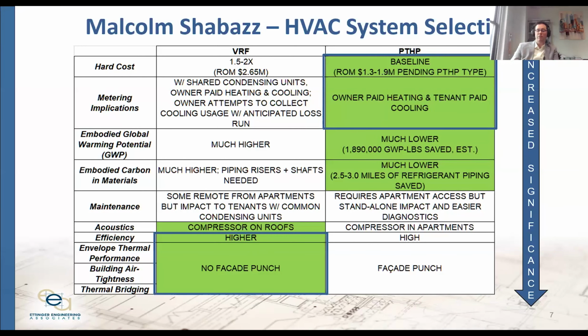there are two prime benefits that a development like this would seek to gain. First, without all of this refrigerant piping, the PTAC system is quite a bit cheaper, and depending on the size and flavor of the building, it's running about 1.5 to 2 times cheaper than the VRF system. The parentheticals on the slide are actual numbers for our project, if you want those for reference.